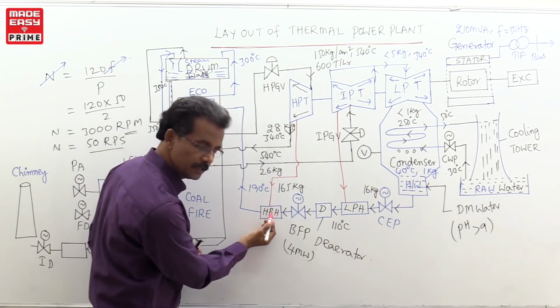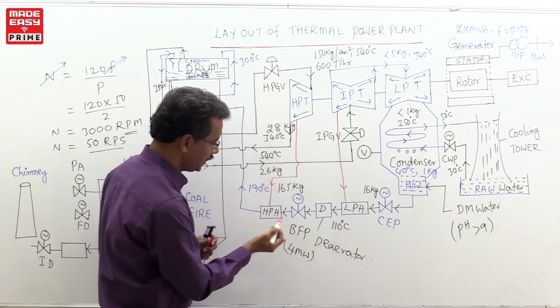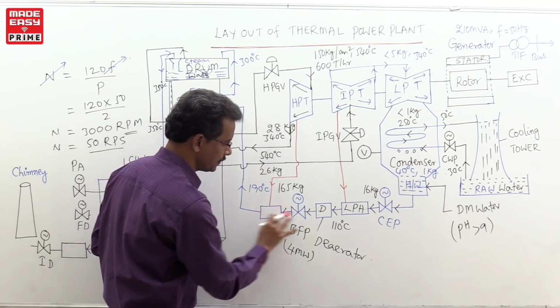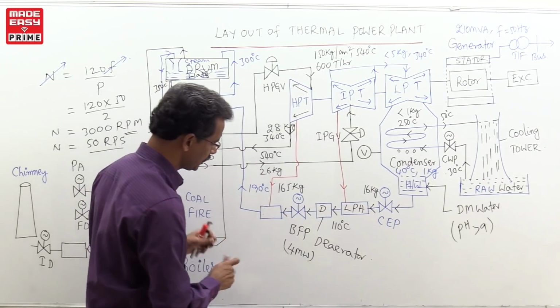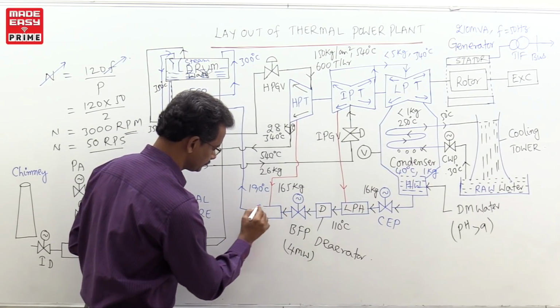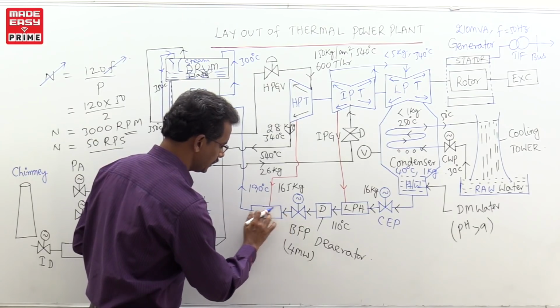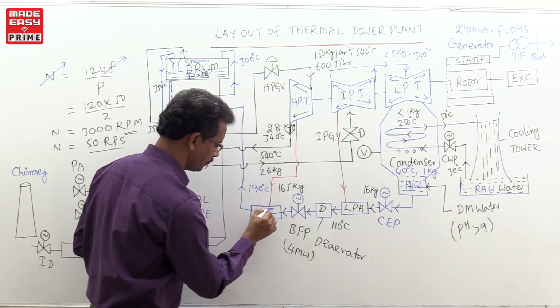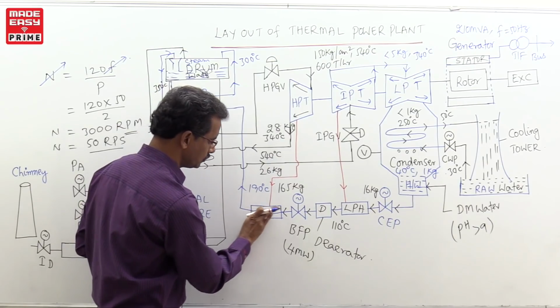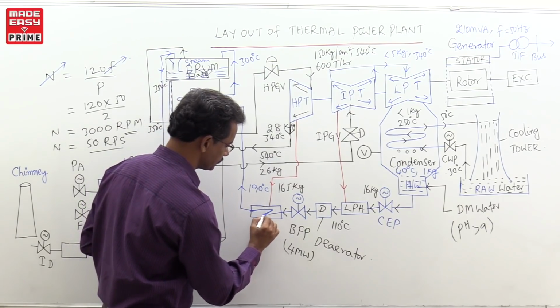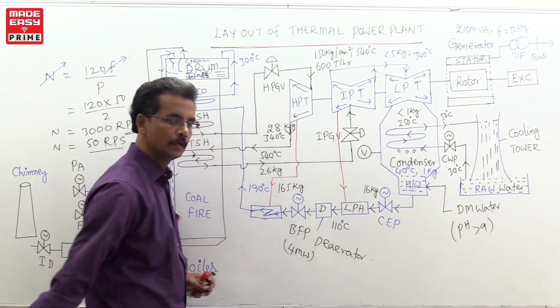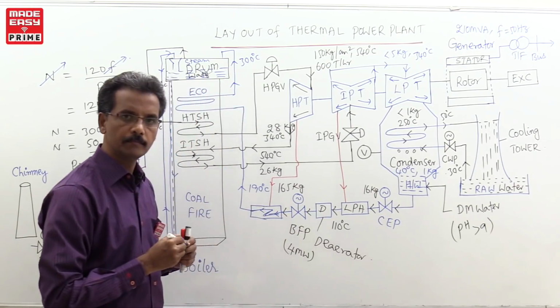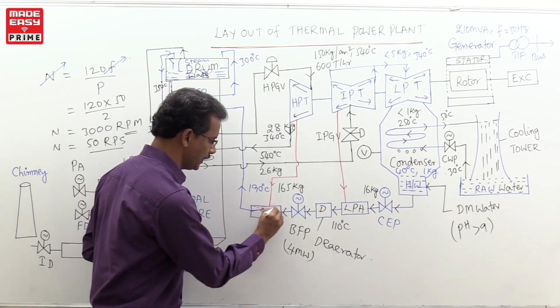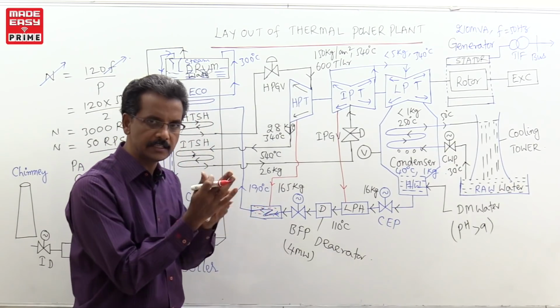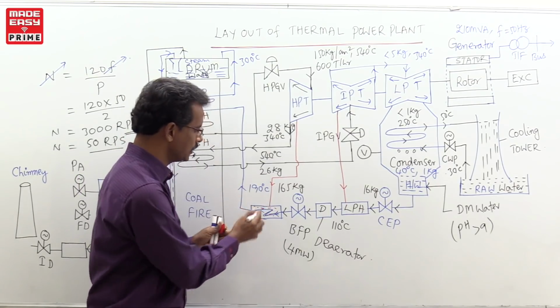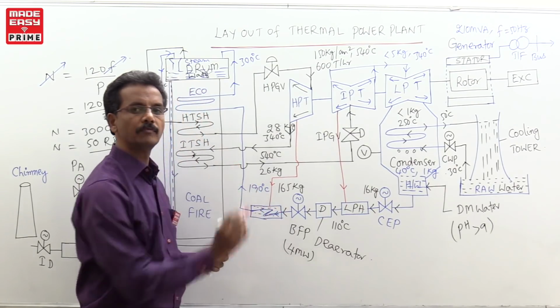Inside the HP heater, there are tubes. Similarly, the LP heater also has the same thing, with tubes inside. So you can imagine like this: this is an HP heater, and here you can imagine this is a tube. Water is flowing through the tube. Steam is coming from the turbine. Steam is accumulating here. What will happen now? The steam energy, the heat, is transmitted into the water, so that the water temperature rises up to 190 degrees centigrade.